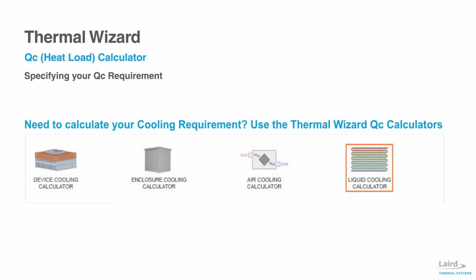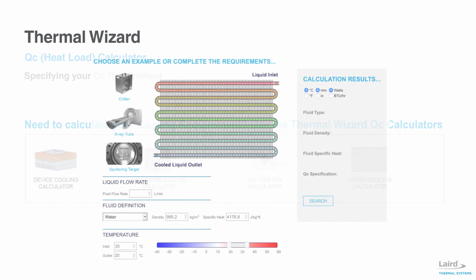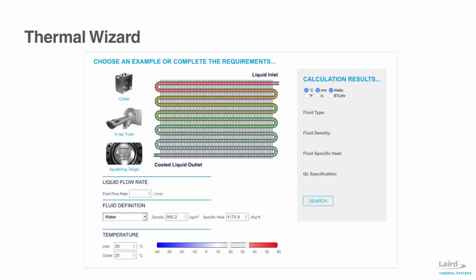If you do not know the cooling requirement for your application, the Thermal Wizard provides a liquid cooling calculator to help you determine the QC requirement. The Thermal Wizard cooling calculator prompts you for all the information necessary to produce a QC estimate. As you can see, there are 3 examples of different sizes to help you get started. Once you have determined the QC requirement, you can utilize the QC slider to specify the appropriate series of thermal management products and select the optimum solution.